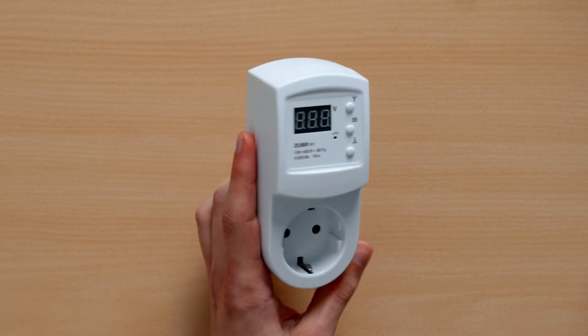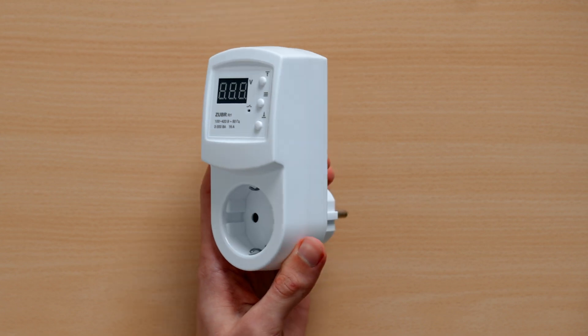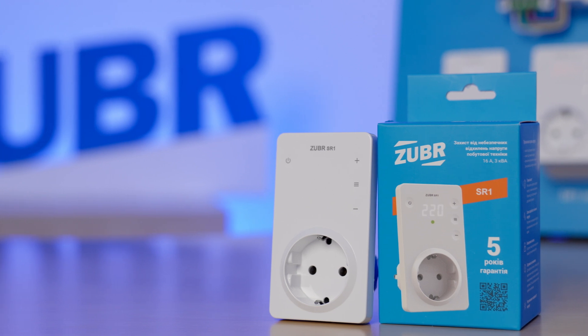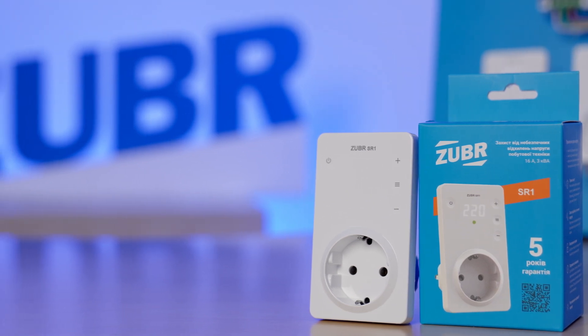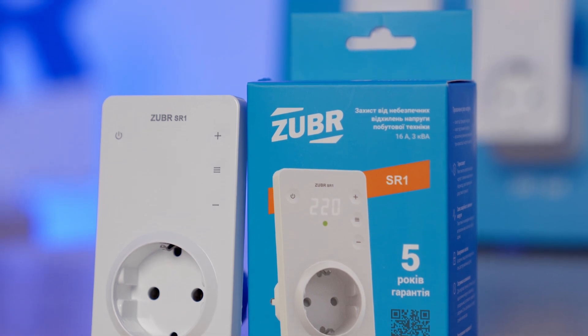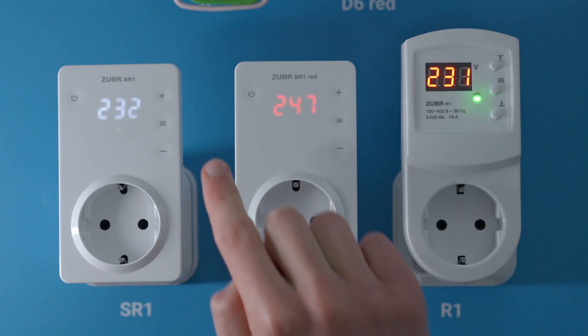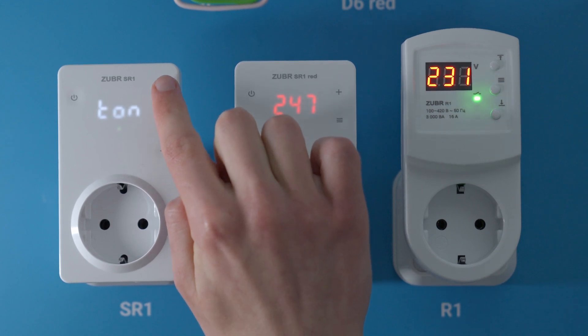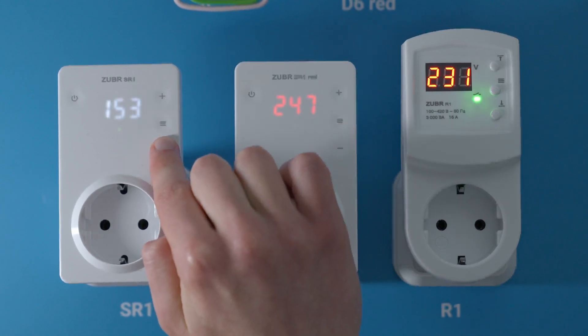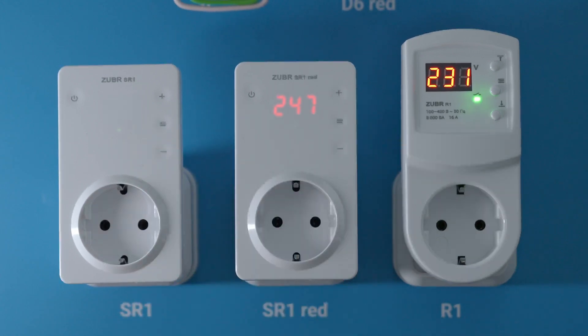Like all other models, the R1 is made from non-flammable polycarbonate. We also have the ZUBR SR1 model — the functions are the same, but it features a refreshed design with a more compact build and sensor buttons. The main advantage of the SR1 is its impulse power supply that decreases power consumption in standby mode. To increase the lifespan of appliances with a compressor, like a fridge, we recommend increasing the switch-on delay time after a voltage spike to an optimal two or three minutes.